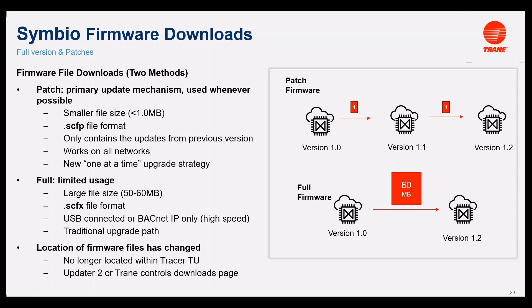The other available file to upgrade the firmware is using a full version. This full version is a large file size — we are talking about 50 to 60 megabytes on average. The format of this file is SCFx, and the only way to do this upgrade is using a USB connection or BACnet IP connection. You can go, for example, from version 1 directly to version 1.2 with this 60 megabyte file. This is the difference between patches and full version.